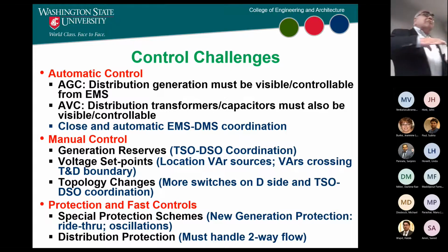The only way you can do this, if you have say 50% of your generation on the low voltage side, is you'll have to know what's going on there. But right now, nobody sitting at the Midwest ISO EMS has any visibility into what's going on in the distribution side. Their lowest voltage measurement comes from the lowest voltage transmission system. So you see why this is a challenge.